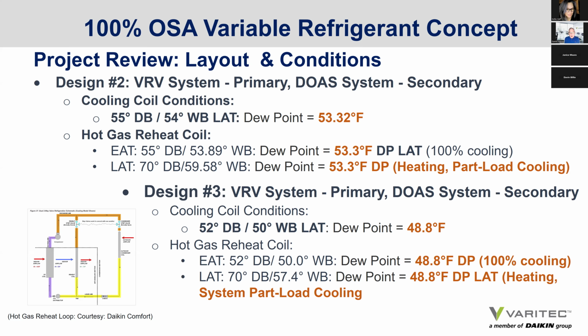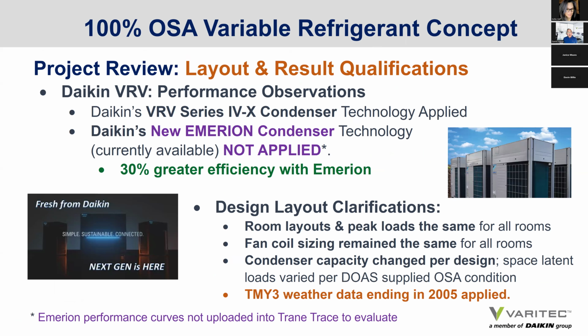It was recommended by our regional sales manager for Daikin Applied, Jay Eldridge. When I asked him the question before writing the article, what we should target for appropriately designed outside air, Jay said, try 52/50. And we did. And that was pretty revealing in what we found out. So let's look at the actual performance.